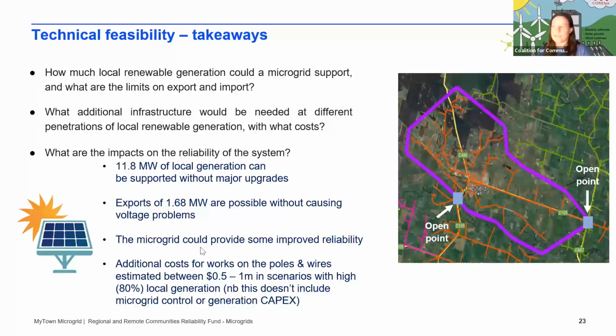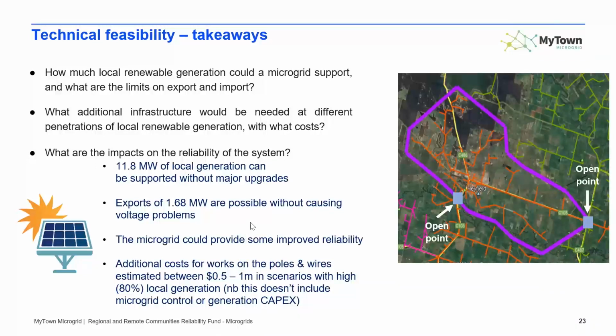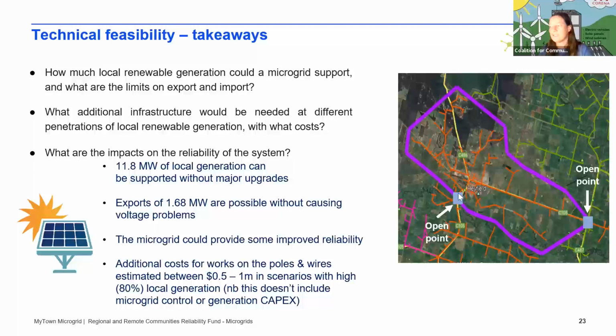The microgrid could provide some improved reliability, but you've still got a problem since some faults occur inside your own system. In our modelling we put half a million to a million dollars into every scenario for extra switching needed on the medium voltage system - you have to automate this switch here and the one on the road coming in. Both need electrical infrastructure and investment, even before you start on storage and generation. So it's a bit of a sunk cost on a microgrid, and it starts to kill things.